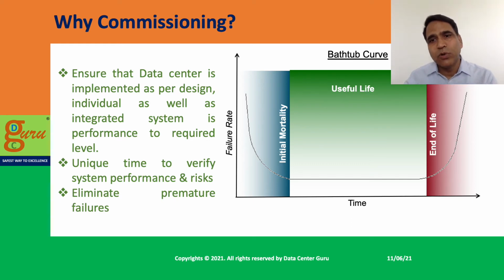So before you go live, ideally all these tests should be done, because once you go live in the data center, it becomes very difficult to do those tests, since you run a risk of data center outages. This makes it very, very important to do the commissioning before you go live. That's what we call a unique time to verify system performance and risks, because you may not get that opportunity again. It's not that you cannot do it later, you can, but there are a lot of risks associated with it.